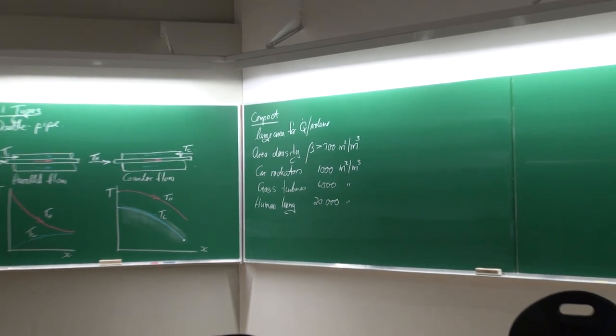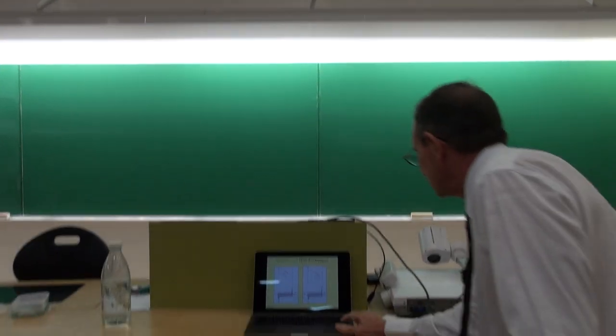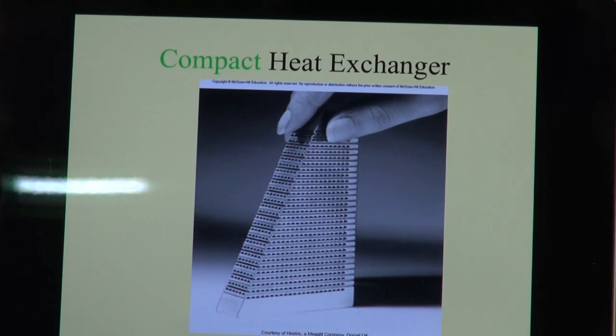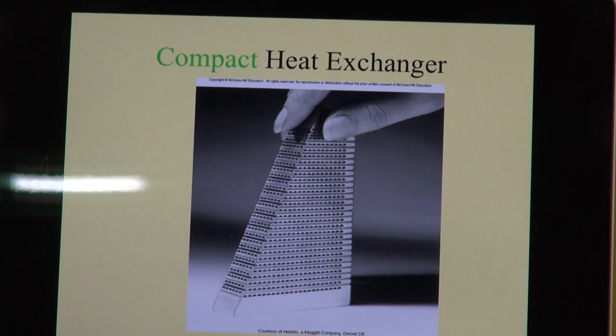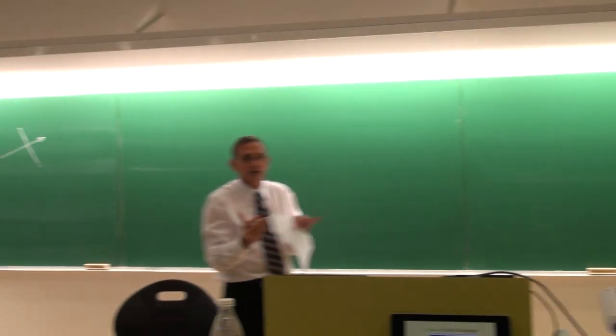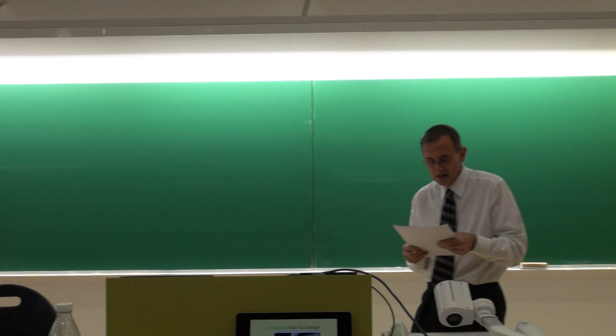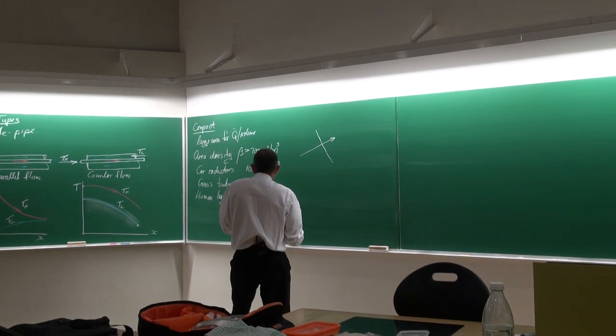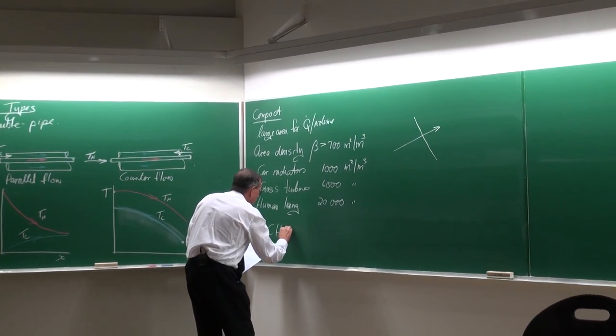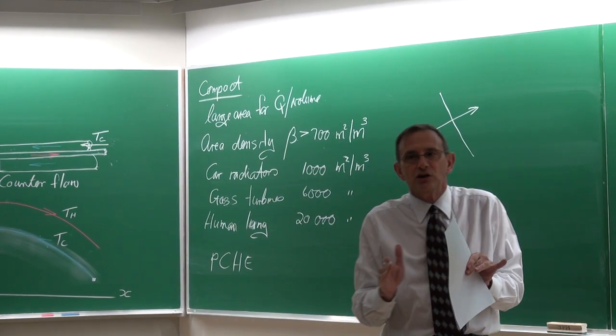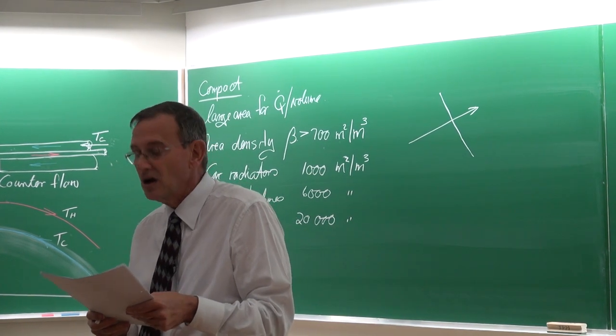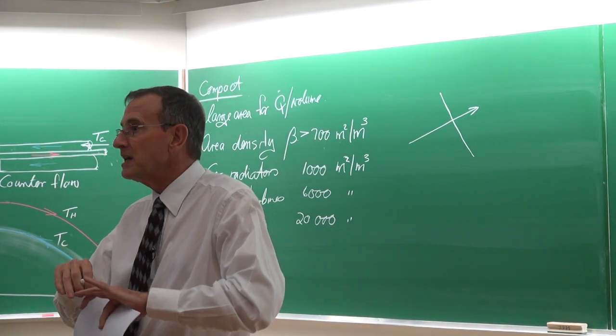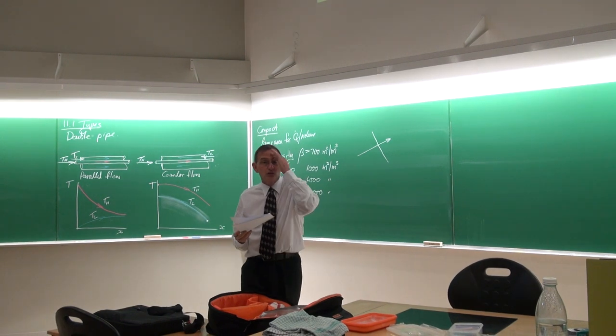In terms of compact heat exchangers, I want to show you a photograph. There are holes in one direction and holes in another direction through the same material. These are called printed circuit heat exchangers — PCHE. They make use of a method of etching to make channels of 1 to 3 millimeters, then diffusion bonding, and they can also generate different patterns in some of these channels.